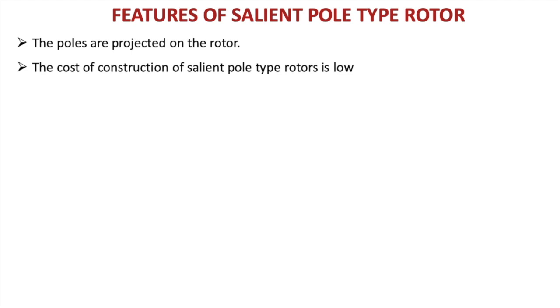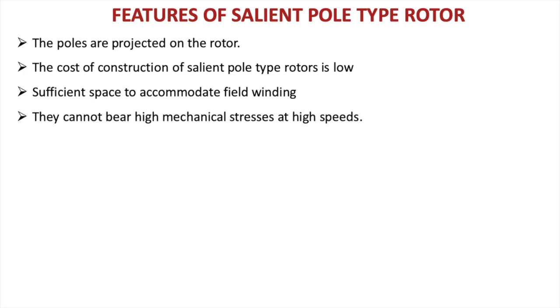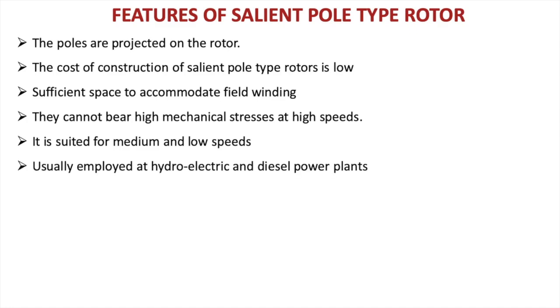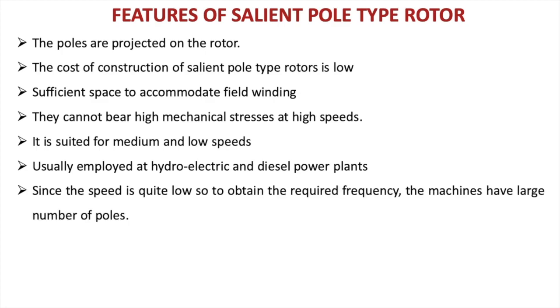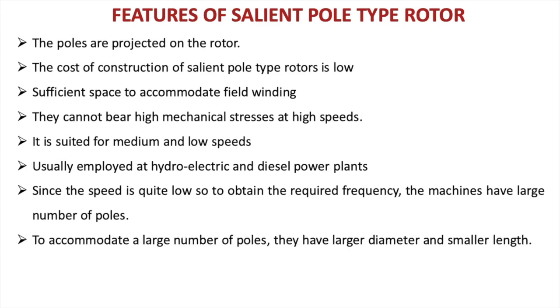Then come the features of the salient pole type of rotor. The poles are projected on the rotor. The cost of construction of the salient pole type rotor is low. There is sufficient space to accommodate the field winding, because it is accommodated on the field pole. They cannot bear high mechanical stress at high speeds. It is suited for medium and low speed rotations, usually employed at hydroelectric and diesel power plants. Since the speed is quite low, to obtain the required frequency the machines have a large number of poles. To accommodate a large number of poles, they have a larger diameter and smaller length.